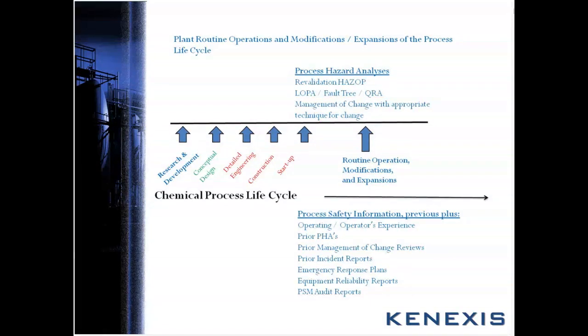So the point is, the safety instrumented function may be added or changed at any of the life cycle changes of the plant. So the SIF requires management and maintenance during the entire process. The safety instrumented system must be managed to meet ISA-84 life cycle requirements as well as the PSM process. So therefore, it's necessary to integrate the ISA-84 life cycle requirements into the PSM process because it draws information from the PSM process on a dynamic and ever-changing basis.